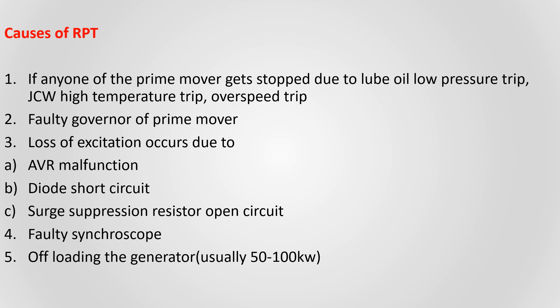Loss of excitation in the alternator also occurs due to AVR malfunction, diode short circuit, or surge suppression resistor open circuit. A faulty synchroscope can also be a cause.